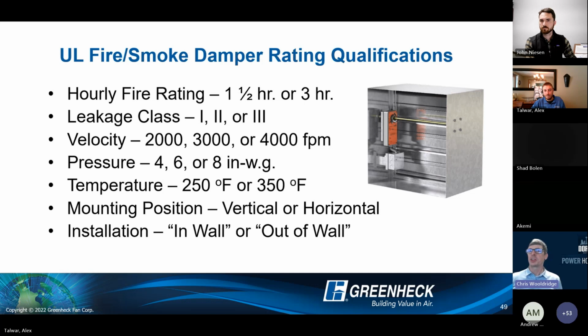While I have you interrupted, we did have another question just a few minutes ago in our chat. For two independent combination fire smoke dampers getting installed side by side in an existing concrete opening, what type of architectural assembly needs to be added between those two dampers? It's kind of a tough one for you. Yeah. I mean, anything that could maintain the rating, I suppose. Yeah, you are right to point out the fact that if you have two dampers in one opening, that's kind of a no-no, right? You can't put them both in there together, but if you can separate that opening into two separate openings, then that gives you a shot. Question being, what do you use to separate those openings?